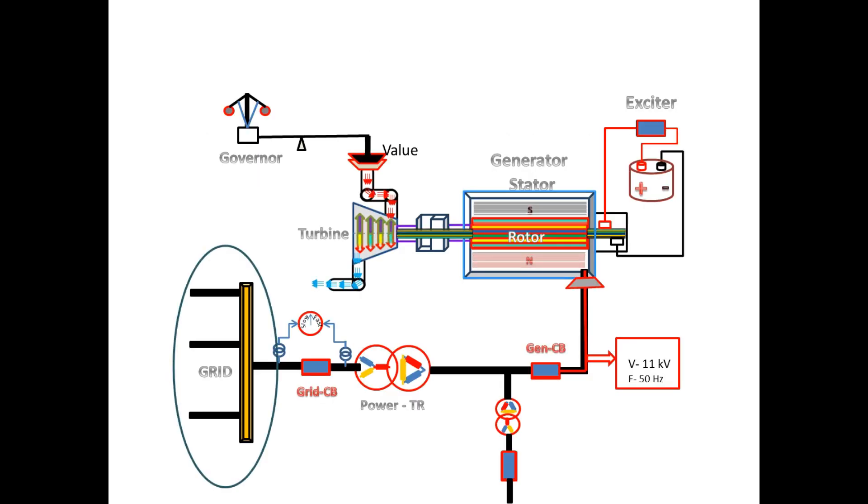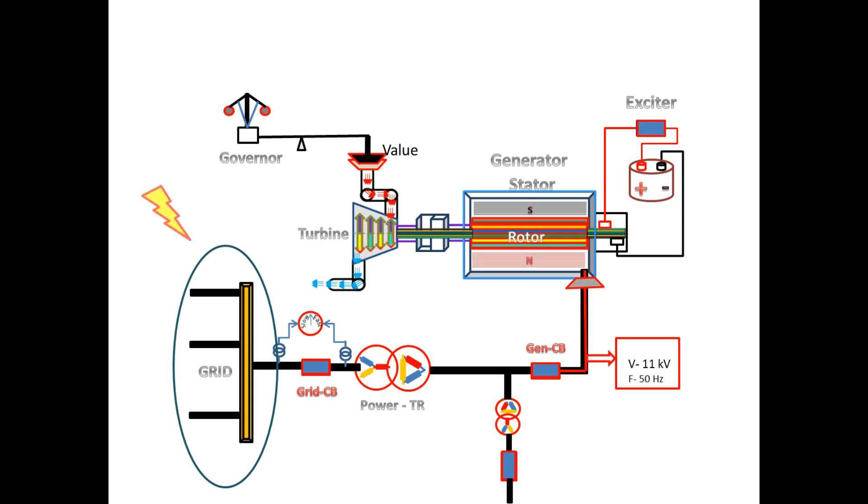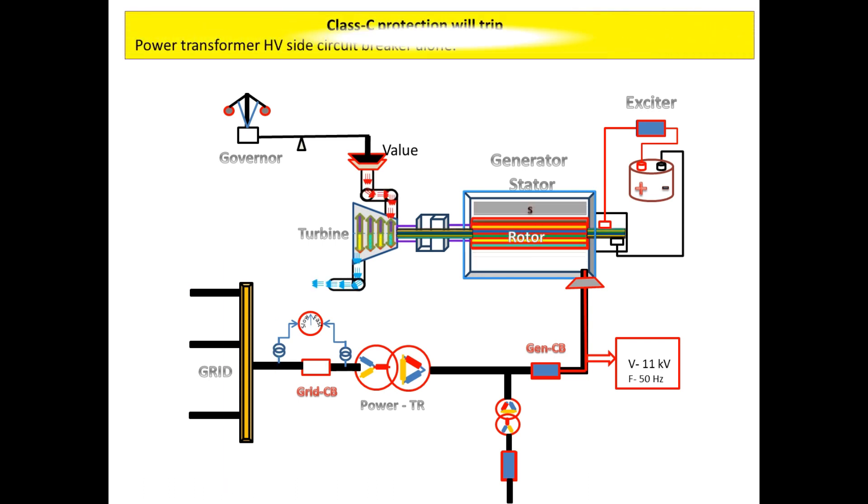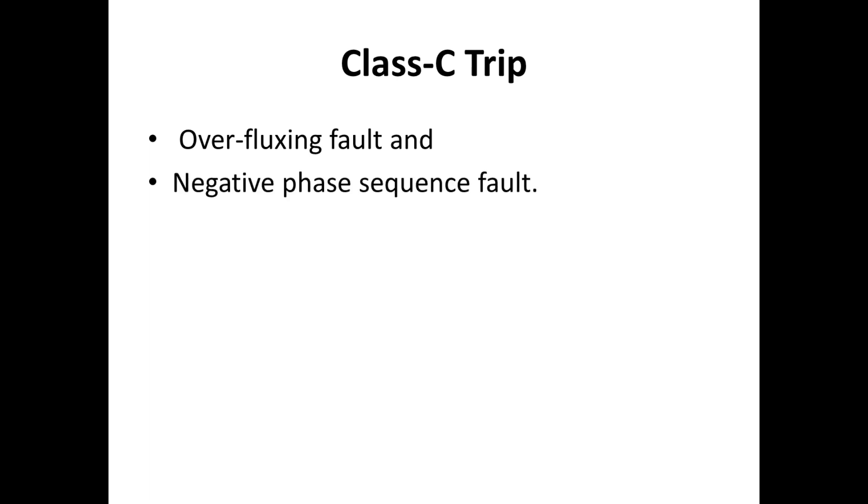For this class, the following circuit breakers have to be opened. The power transformer HV side circuit breaker alone, if it is open, is enough. I have shown some of the protections which belong to Class C: overflux fault and negative phase sequence fault.